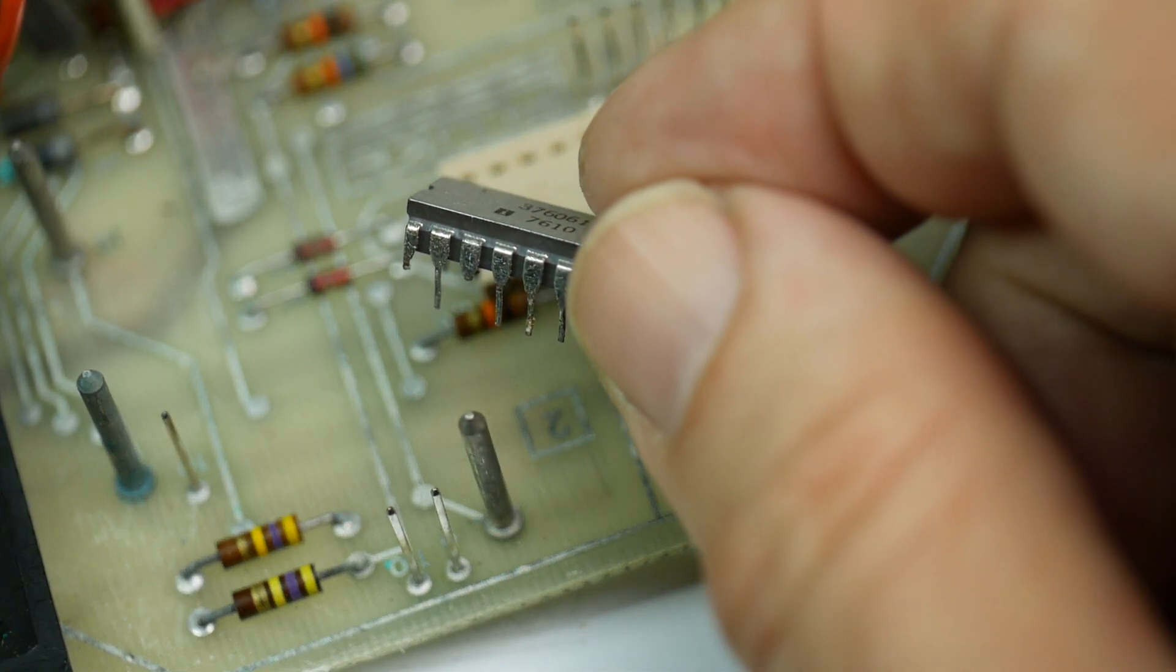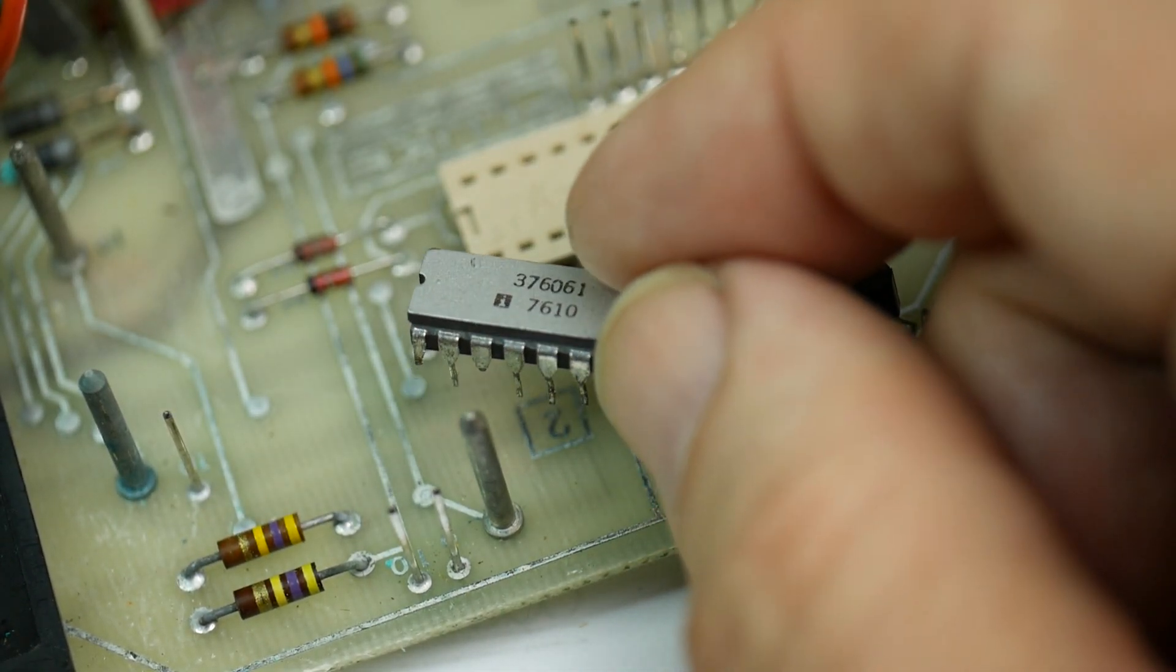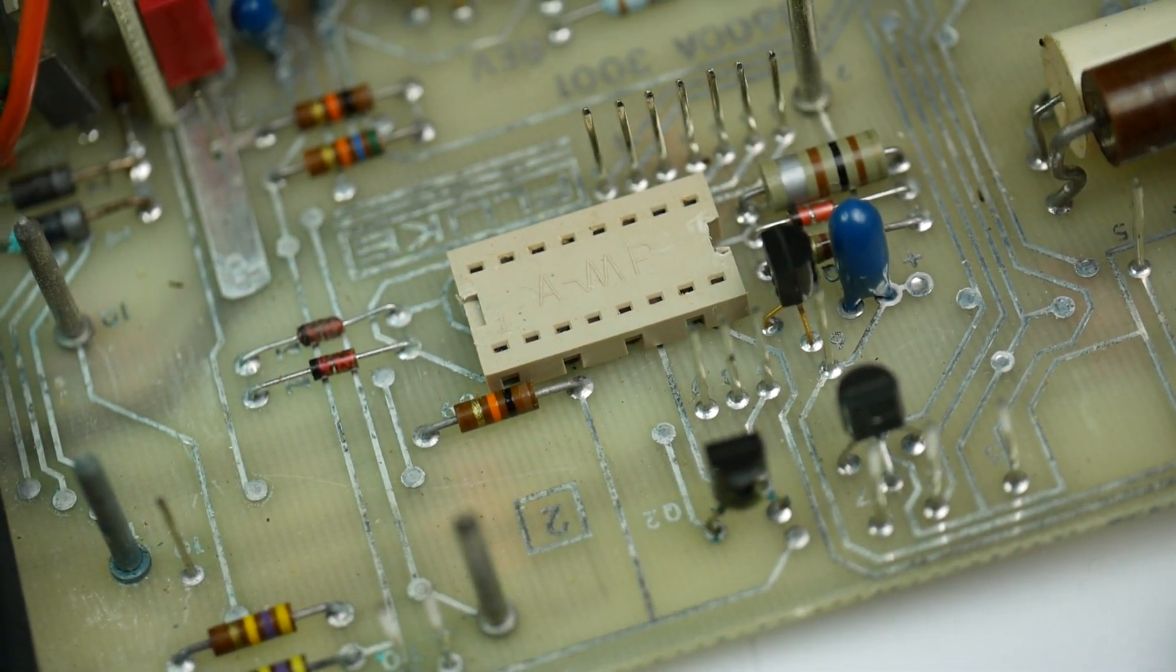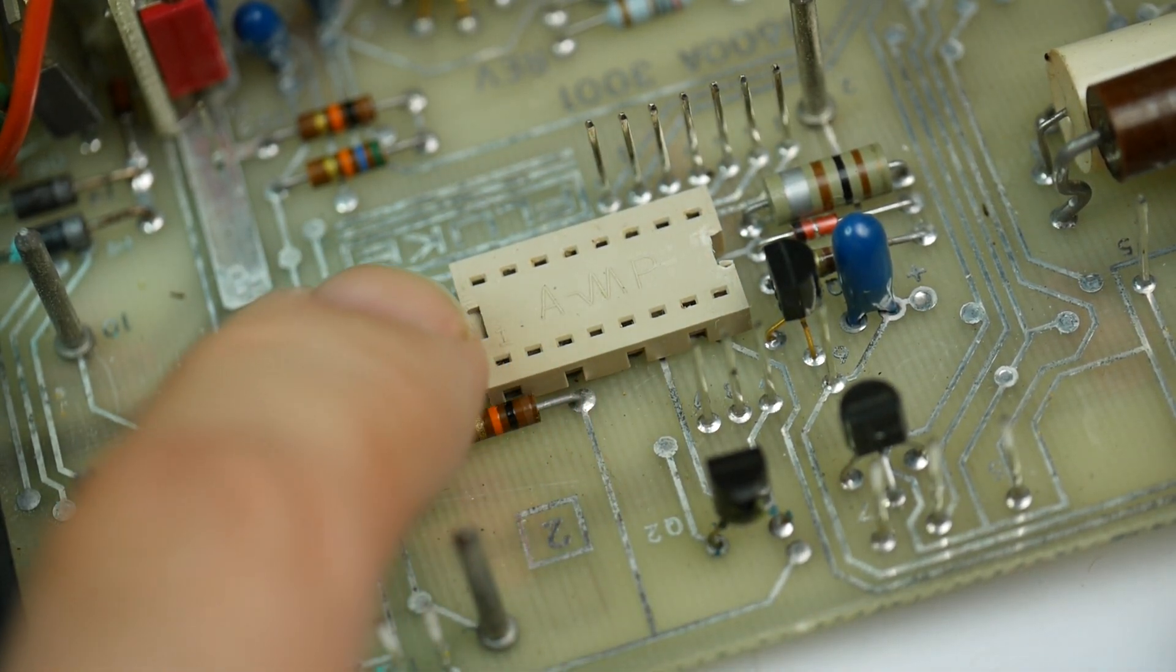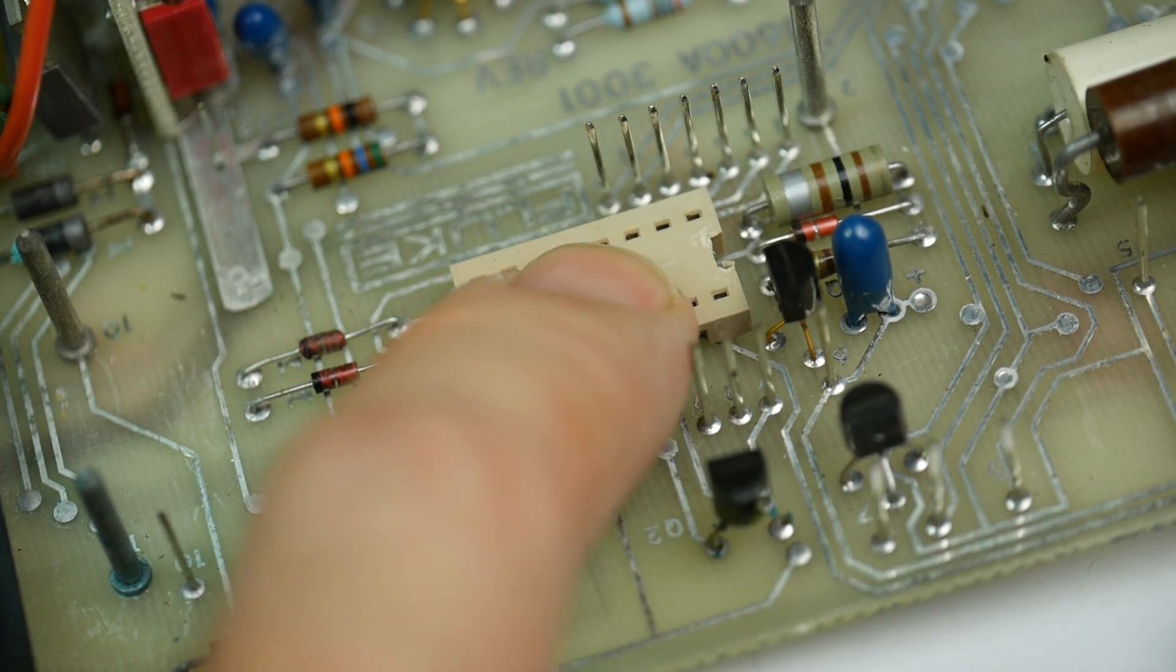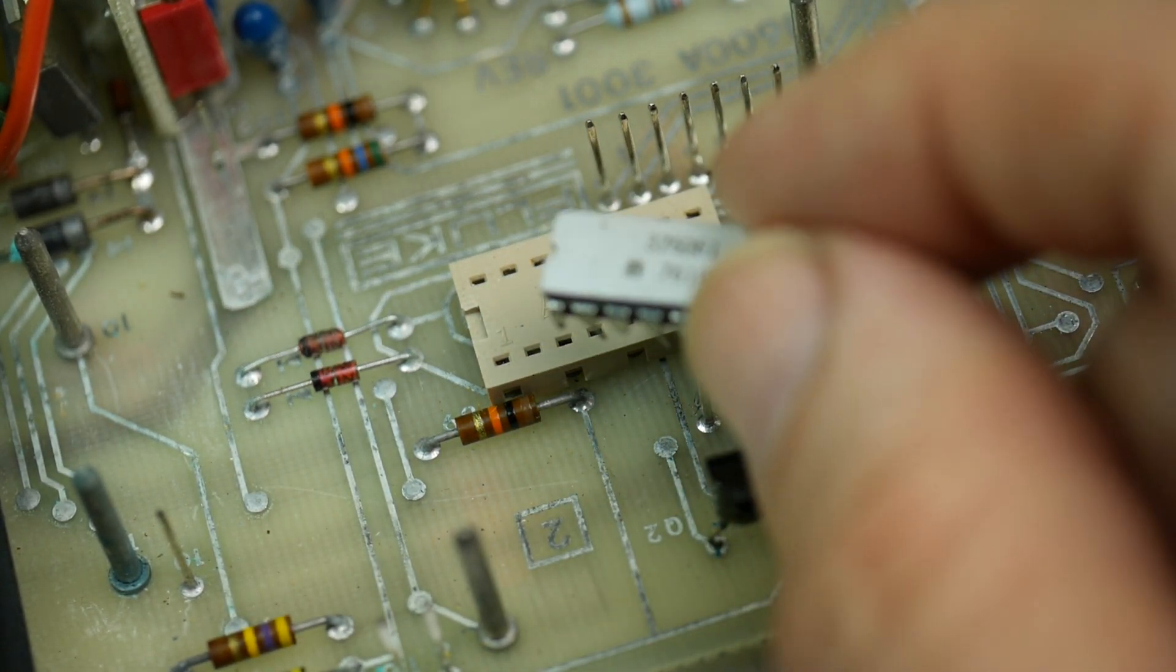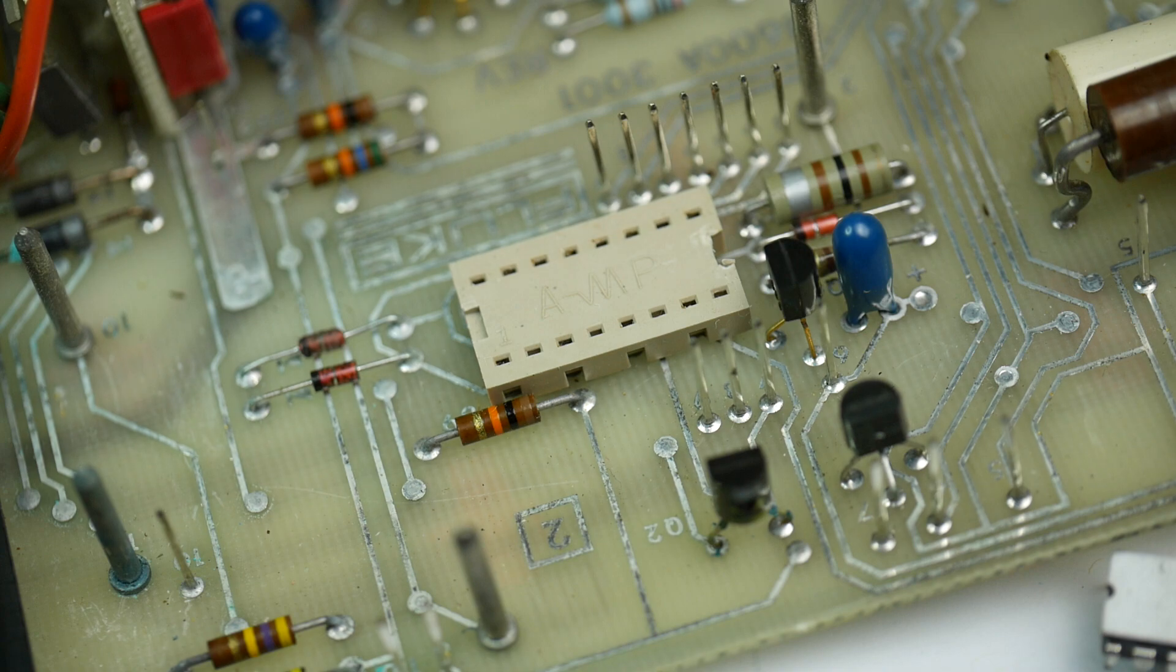Well, I could. What I'll probably end up doing is soldering this down to a DIL header, so that that DIL header will have good probably gold plated pins. And then we'll have to put that chip and header into a socket. Now, the pieces of metal that broke off from those pins are probably still in the holes in this socket. And I don't trust the condition of the socket anyway. So I really need to remove this socket. I have to desolder the socket from the board. And having desoldered it, put a new one in, a modern, probably a turned pin socket, and then plug the chip, plug the existing chip, on a header into the new socket. Quite a long process, quite a fiddly thing to do. But I think that's the only way we're going to find out what else is wrong with this thing. Once we've sorted out the range selection, I think then we can go on and actually make the thing work.